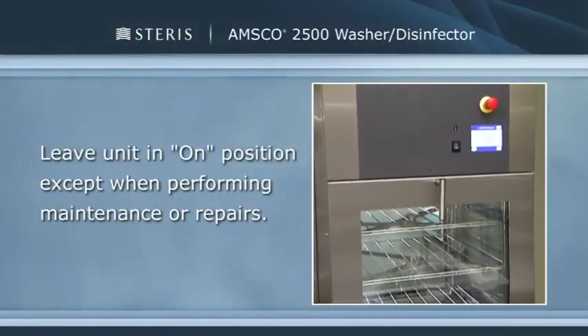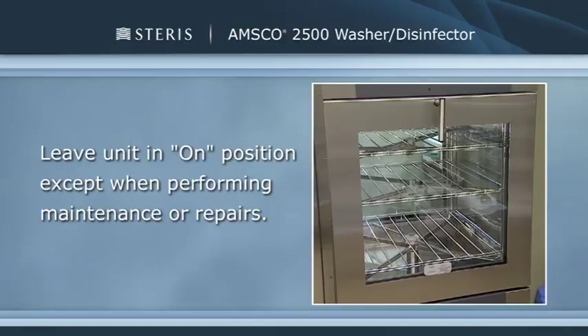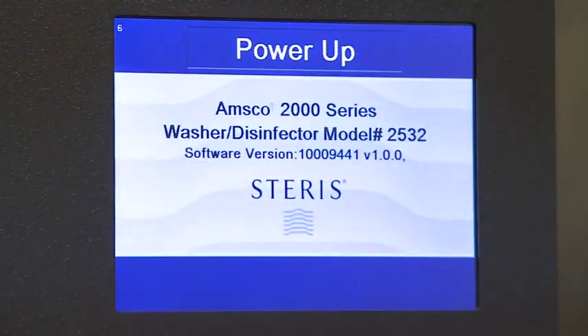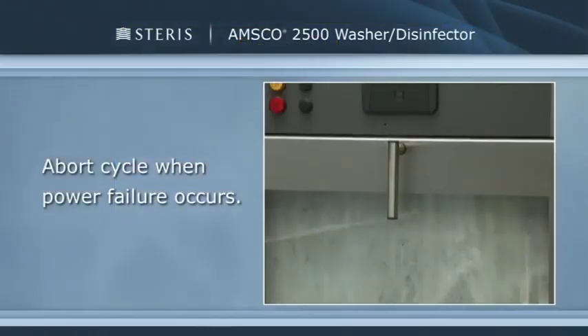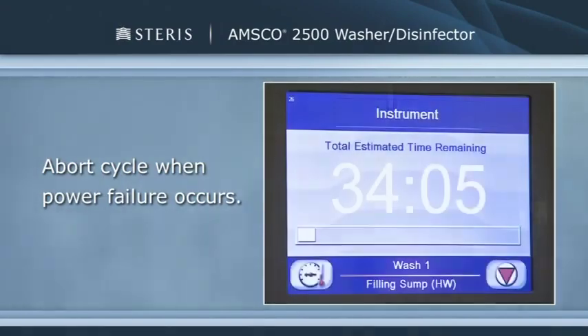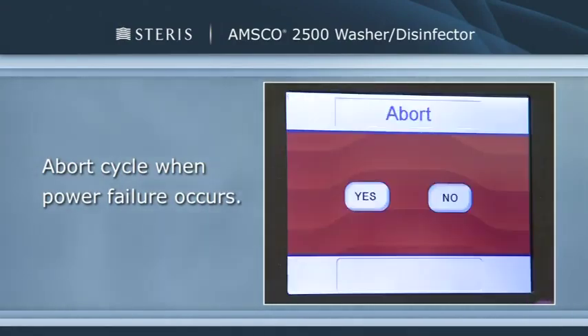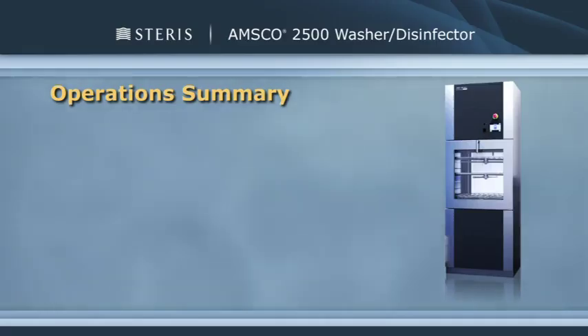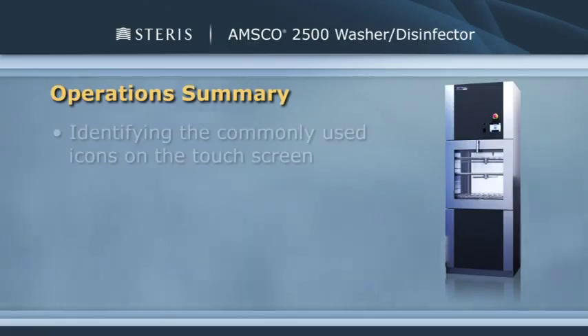It's important that the washer disinfector remain in the on position at all times, except when performing maintenance or repairs. In the event of a power failure, the power up sequence begins when power is restored. If a power failure occurs during a cycle, the cycle must be aborted once power is restored. Doors cannot and should not be open unless the cycle has been successfully completed. In the case of a power failure and it is necessary to open the load door, call a qualified service technician.